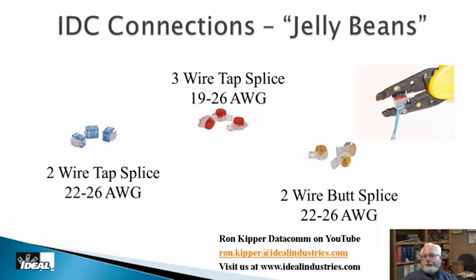So what the red ones do for me is they tap a line. And basically I would take one of those conductors I want to tap, I'd cut the cable, take those 2 ends and put them inside of a red one. And the red ones have a hole for a third conductor, which would be tapping off to that phone I'm going to feed. And when I crunch it down with a pair of pliers, it'll make them all 3 again using those IDC connections. And we sell a plier, and everybody else has got a plier, and I can tell you a pair of channel locks will probably work fine as long as you don't crush the little plastic housing of the jelly bean.